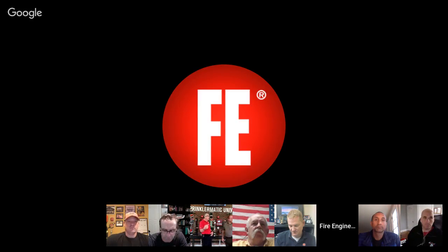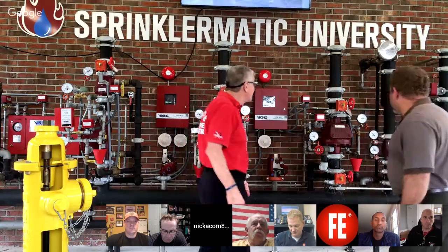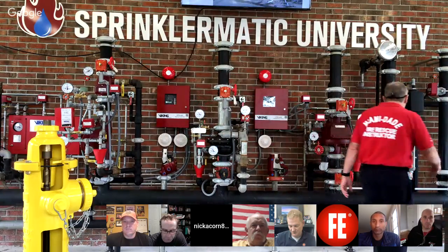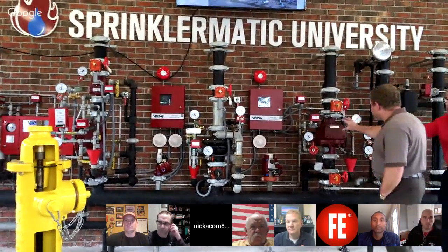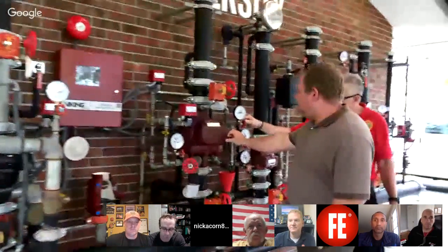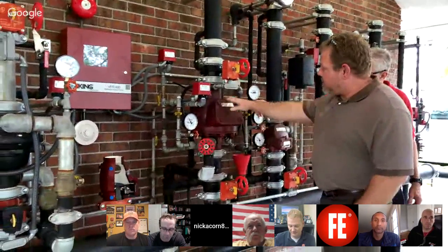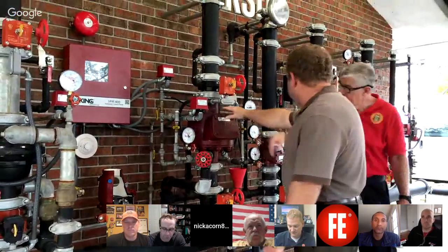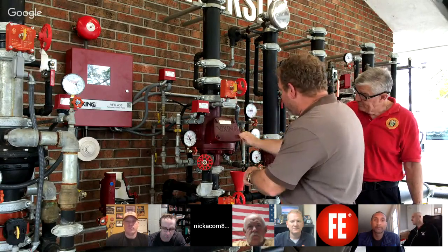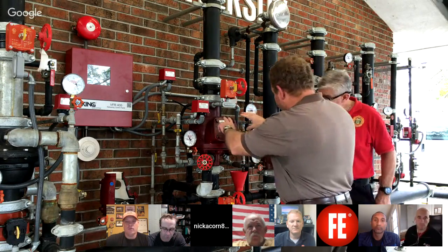Julio, if you would, we're going to go back to the old school water motor gong. We actually have to physically take the face off. Typically, we'll leave one bolt in, slide it open, and we can put our hand inside, unlatch it, pull it down. We have basically a tire iron, and we reset the valve, close it back up, drain the water, put the air back on, watch that differential, and then put it back into service.